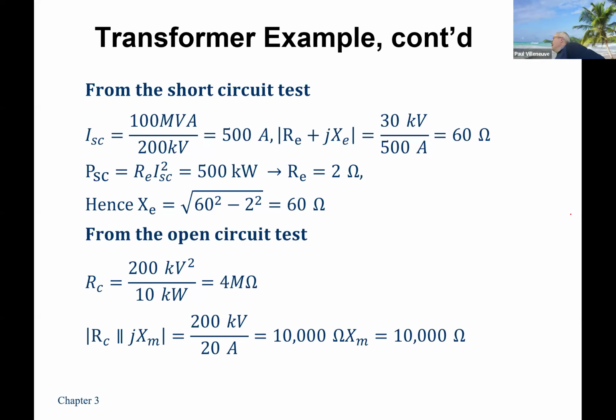Close enough. For the open circuit test, I did just the 200 kV here just to see you can do it. But realistically, in the real world, you'd be doing it on the 80 kV side. So I've got V squared over P, which gives me my R, 4 mega ohms. And then to solve for the parallel combination, my XM gives me 10,000 ohms. And you will note these values here are way smaller than these values here, which is what it should be. You should always have very small values for RE and jXE in comparison to your RC and XM. If they're big, then that means you're going to have a pretty lossy transformer, and it's not going to be a very productive or a very efficient transformer.